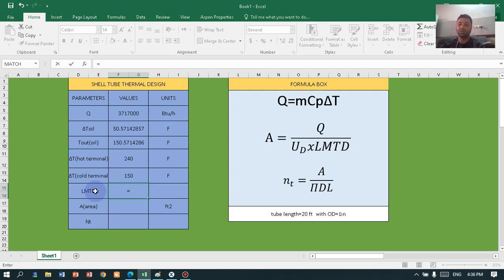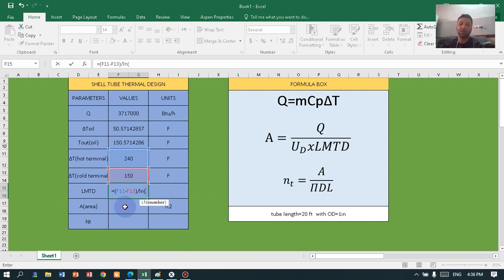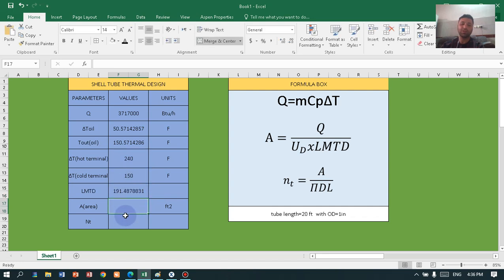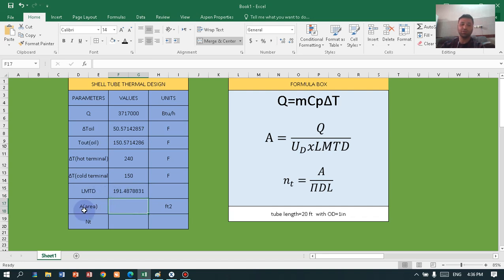Now let's calculate the logarithmic mean temperature difference (LMTD). Press equal, open the bracket — hot terminal minus cold terminal — close the bracket, then divide by LN of the hot terminal divided by the cold terminal, close the bracket, and press enter. We now have the log mean temperature difference.